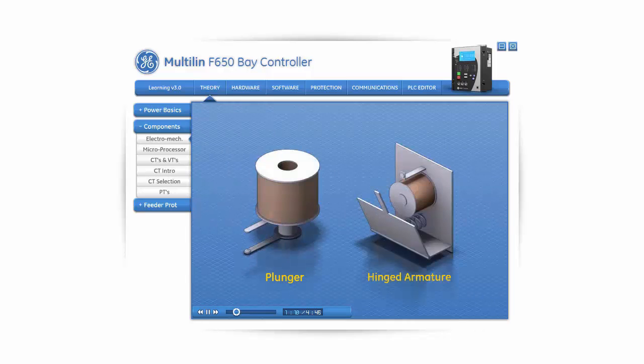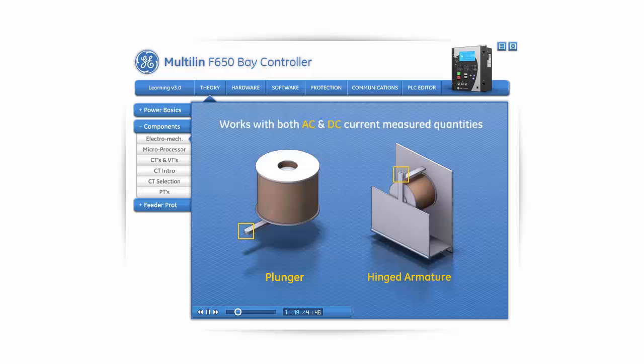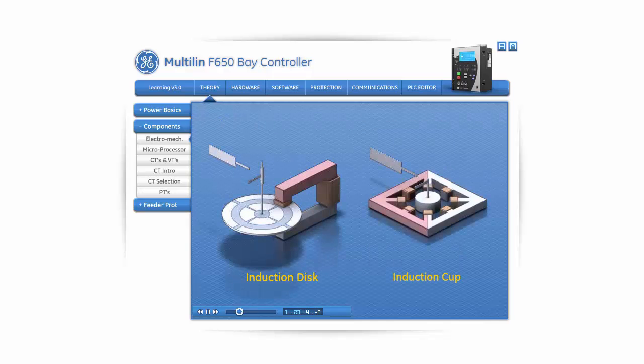The plunger and hinged armature operate under the principle of magnetic attraction. The armature is attracted into a coil or to the pole face of an electromagnet. This principle works with either alternating or direct current measured quantities. The induction disc and induction cup work under the principle of magnetic induction. Torque is developed in a movable rotor in the same way that it is produced in an induction motor, which means that they can only be used with alternating current measured quantities. Now let's quickly review the theory of operation of each style of electromechanical relay.